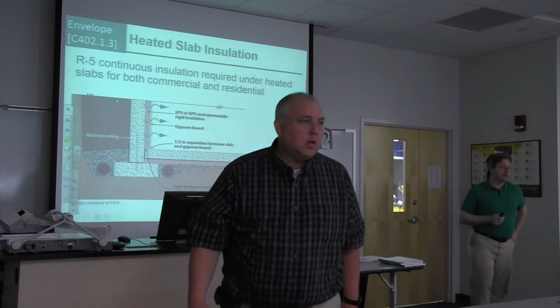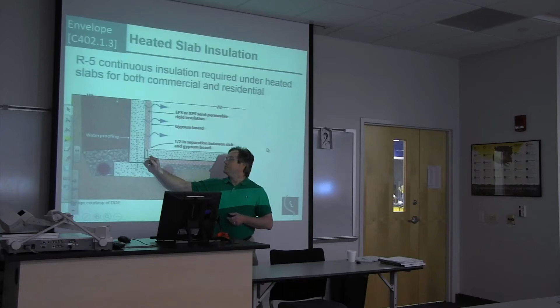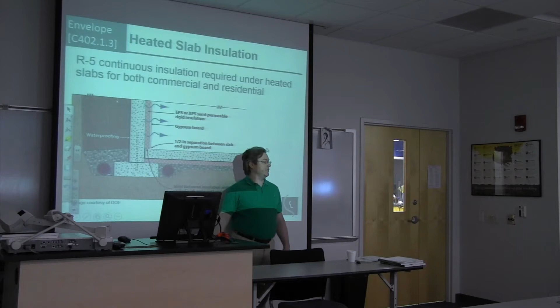Well, this is a heated slab, so they're looking at the insulation down here, which is below grade. So you've insulated that wall from grade, but there's definitely potential for a thermal bridge if these touch and there's not some kind of joint between them. Technically, like Kevin said, that L coming through the slab should be full insulation, chamfered at the top, with the wall insulation intersecting it above.